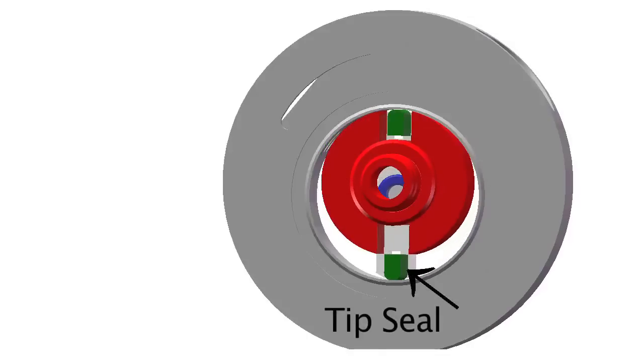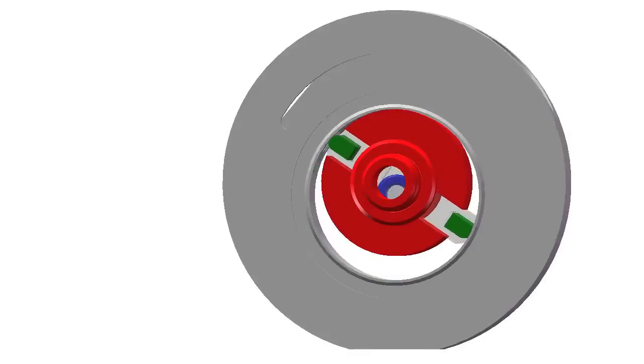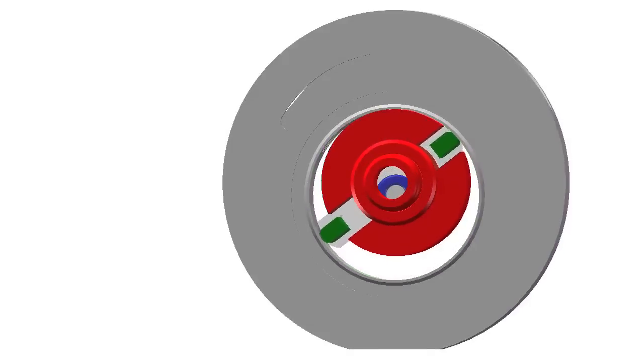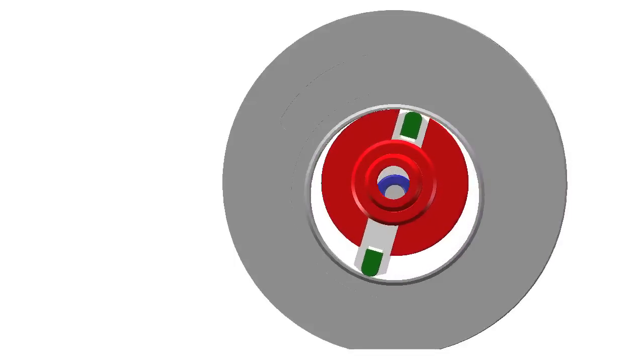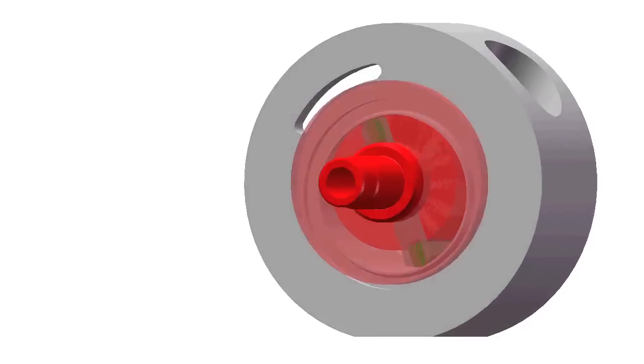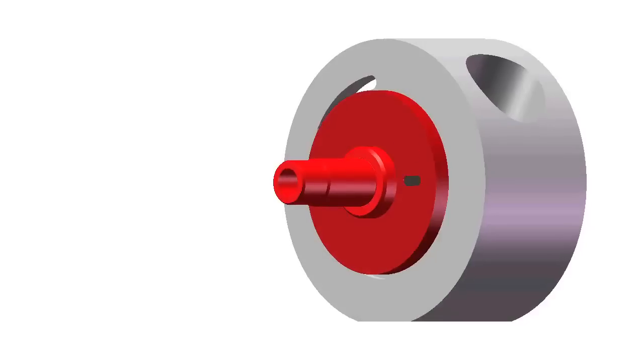The tip seals are placed in slots at the ends of the vane. They are pressure activated, providing a compliant seal between the suction and compression chambers. Because the tip seal spans such a small gap between the vane and the housing bore, it experiences extremely low forces. As a result, the tip seal can be constructed of a low friction, wear resistant plastic alloy.